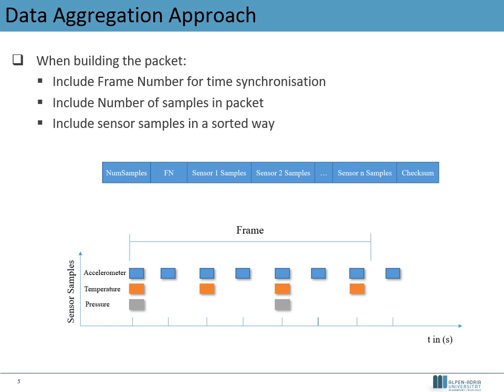The packet built by the transducer consists of the following parts. First is the overall number of samples in the packet, then a frame number which counts the current tick of the base rate. With those two values, the packet can be reconstructed at the base station. Then the samples of each sensor are appended in sorted, chronological order — first all samples of sensor 1, then sensor 2, and so on. Finally, a checksum is added to confirm correct transmission or request a retransmit if the packet is corrupted.